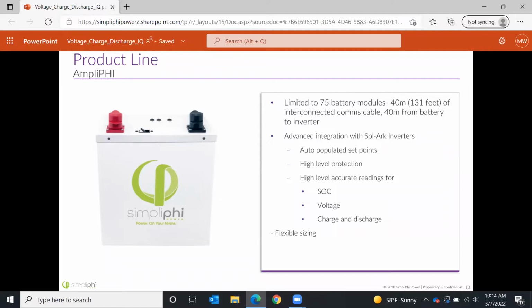In addition, last but not least, it's going to have cold weather protection, so it will not allow you to charge it below freezing when you're paired with a communicating inverter. Again, it's going to tell that inverter to dampen down the charge, and if it doesn't listen, it's going to open circuit internally. So it's a much stronger, more intelligent BMS that's got external communications as well as added internal protections.